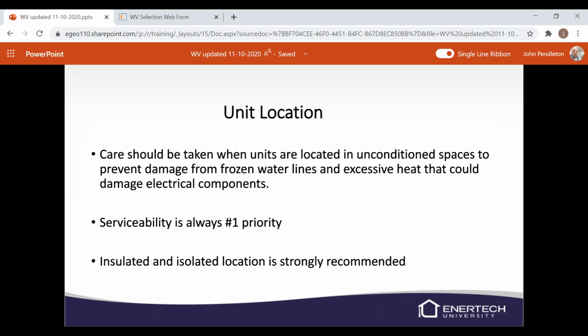Unit location. Care should be taken when units are located in unconditioned spaces to prevent damage from water lines or excessive heat. A humid area is not a good area either. It's going to cause boards to fail prematurely, rusting of the cabinets, things like that. So I would not recommend putting it in an unconditioned space, like a crawl space or an attic. A garage is probably okay. It's going to stay warm enough in there, and it's not going to have any real effect from the weather in there. So a garage may be okay.